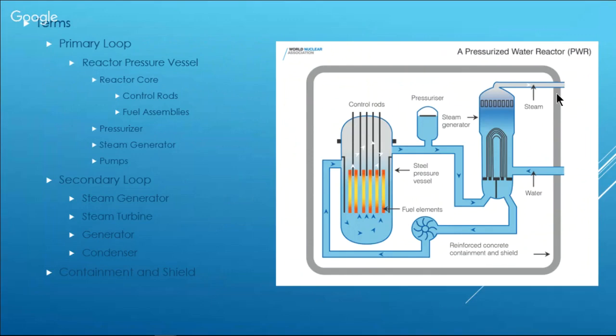So you have more steam drawn off here, more water going in here, which means you have more water crossing these U-tube bundles. That means more heat exchange from the U-tube bundles to the secondary flow. This causes water from the primary coolant loop to cool off faster, resulting in a lower temperature at the exit of the primary coolant loop. This causes a lowering of the temperature, called T cold. So you have more energy coming out here, and the water goes down to T cold equals 430. So it drops 10 degrees.